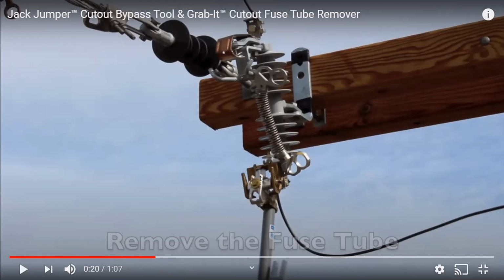So these fuse barrels, and this one didn't travel too far, can swing backwards a little bit. The eye of the fuse barrel down here at the bottom and the cap will make contact with the ground that's on the underground primary, and you're going to have a phase to ground fault. So be careful with these. Make sure that you have plenty of clearance at the bottom before you open up the fuse barrel.